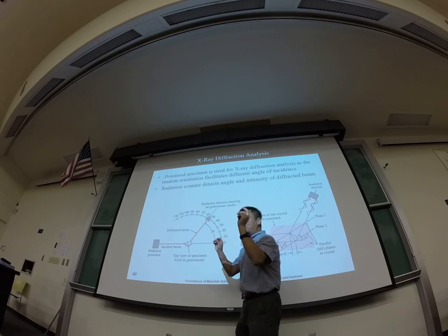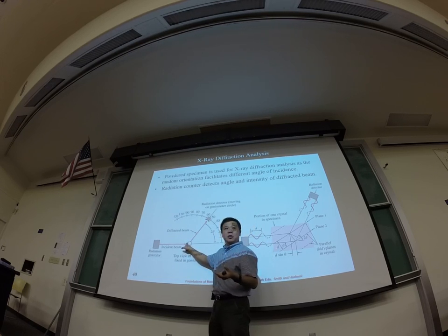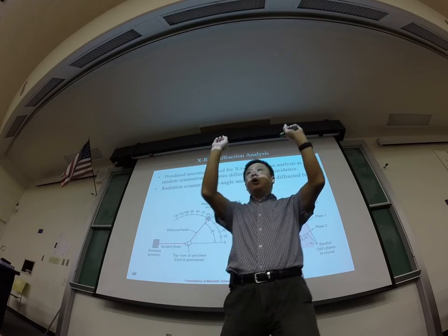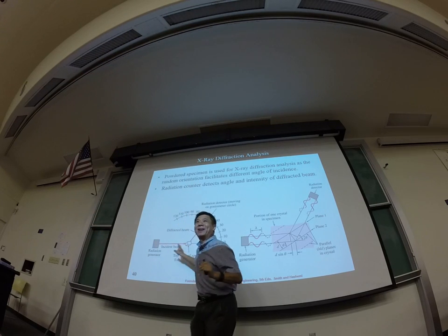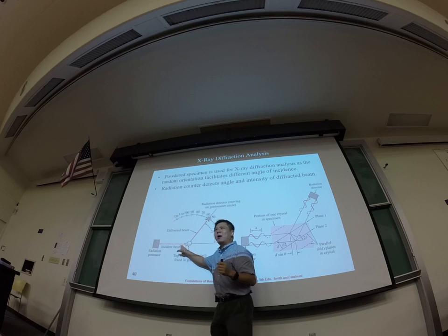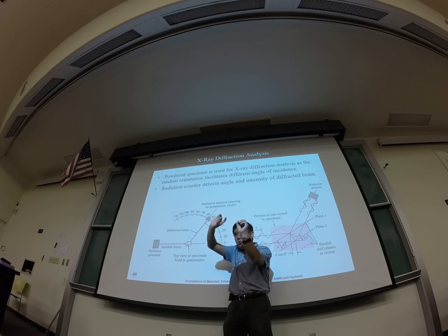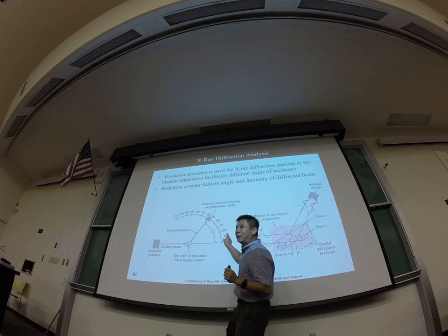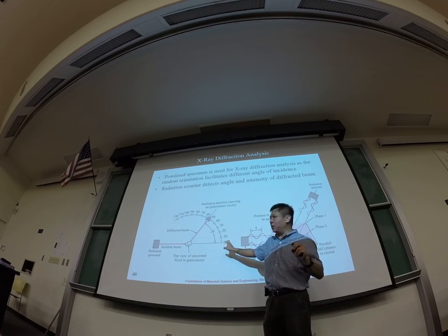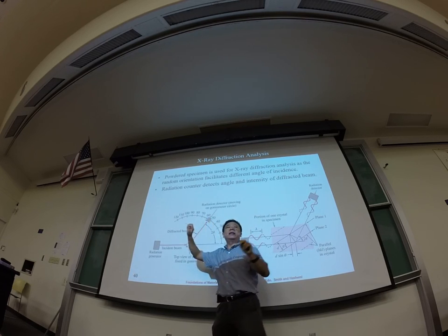So that means when you put, say, 1 gram of your metal sample in the specimen chamber, each of the particles could have a different crystal plane facing the X-ray. Don't forget, in 1 gram of sample, you have millions of particles. Each particle has a unique plane facing the incident light. So when you try to detect what happens here, you use a moving device. Your detector will move along different angles and then read out.